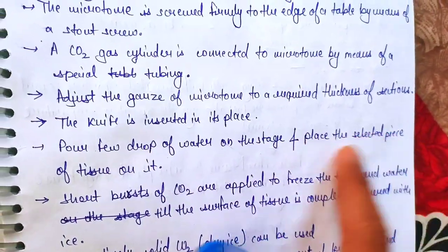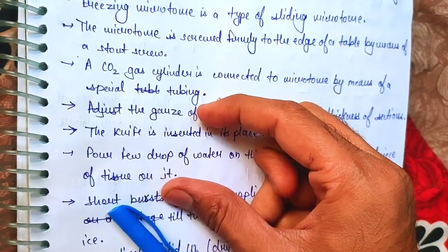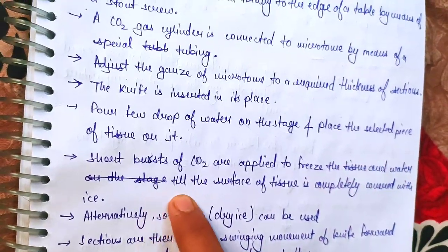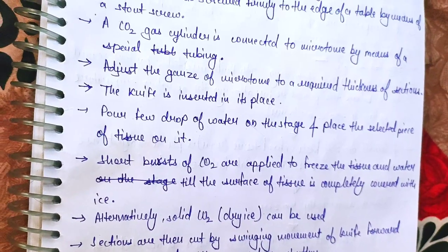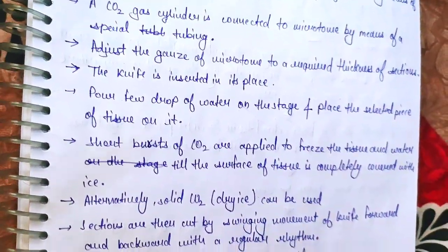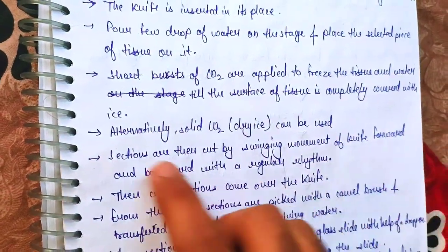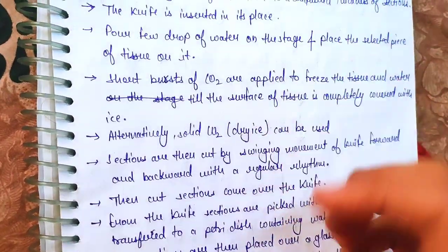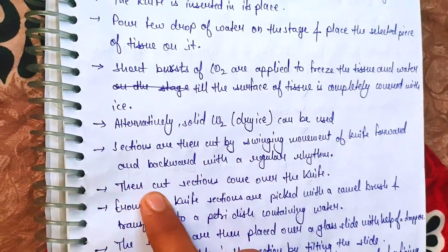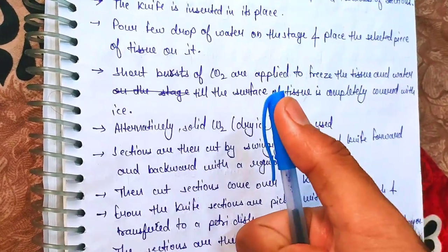Pour a few drops of water on the stage and place the selected piece of tissue on it. Then short bursts of CO2 are applied to freeze the tissue and water until the surface of the tissue is completely covered with ice. We can also use dry ice as solid CO2. Then, using the knife, the sections are cut.